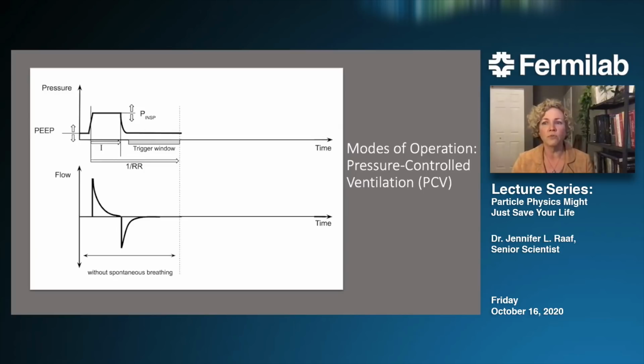So for example, if you set a respiratory rate of 10 breaths per minute, then each breath cycle, which is 1 inhale plus 1 exhale, would be a total of 6 seconds long. So if you then said you'd like the exhales to be twice as long as the inhales, that would be an inhale to exhale ratio of 1 to 2. And it means that you'd have a 2-second inhale and a 4-second exhale for each breath cycle.